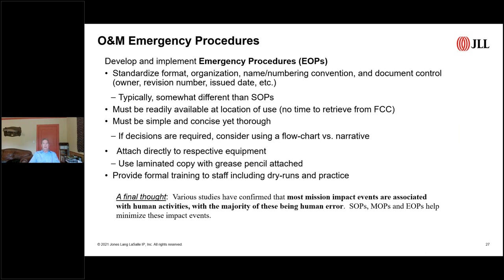And of course, these procedures need to be trained. They should do dry runs and practice these procedures as realistically as possible. I know some mission critical sites that once a year will do a pull the plug test. They will literally kill the power to the building and watch that it operates correctly. They do that as both training and retraining for their staff, to ensure the building will respond and work in a controlled manner with all their contingencies in place, so they can back out if something goes wrong, and to prove to themselves that the equipment in the building is reliable.